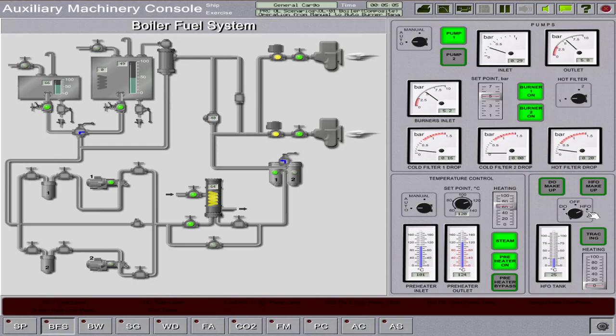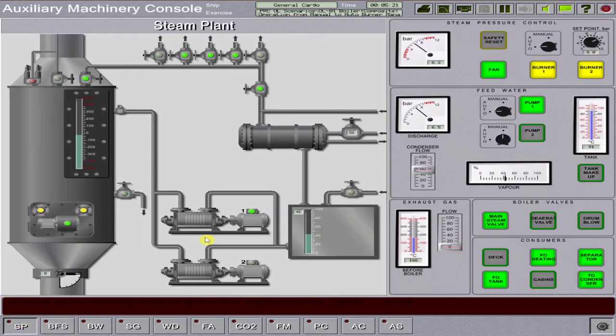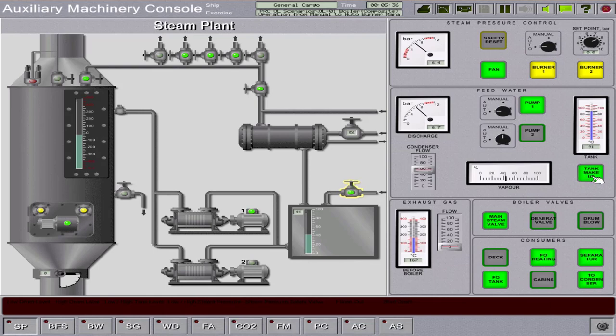Afterwards, open the tracing steam line and adjust heating to your heavy fuel oil service tank. Then go back to the boiler and monitor every parameter. Do not forget to fill up the condenser tank level by opening the tank makeup valve. Once you have opened it, monitor the tank level. The maximum level is around 80 to 90 percent, then close the makeup valve.